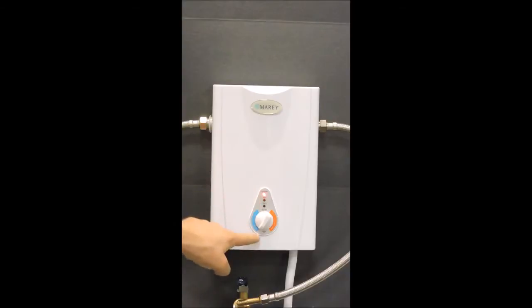Turn on the breaker to allow power to the heater. At this point, the standby light should be the only light that illuminates. Twist the knob clockwise to the 28 amp position. When you turn on the hot water faucet, the heater will activate upon water flow.